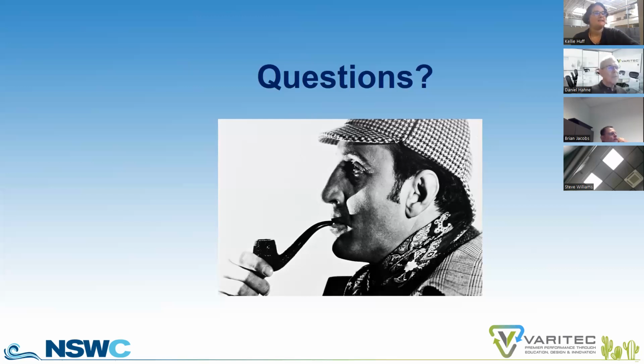Thank you. All right, so the first question: what are typical airface velocities out of an active chilled beam? We normally see, and again it depends on the amount of outside air and the application, anywhere from 120 to 150 feet per minute.